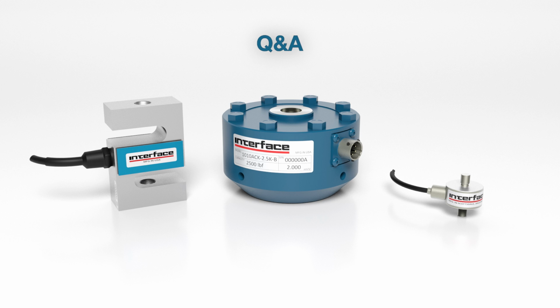Does the 150% apply to all models of load cells? This is going to be a model-specific question. It's going to be referenced on the data sheet for each specific load cell. Again, the recommendation is to size the load cell so the application doesn't require exceeding the actual rated capacity of the cell. I do want to say that a lot of our lower capacity minis, which wouldn't be the low profiles, do have higher overload. We are aware that as capacities go down, it's often easy to damage a sensor just installing it. So our SMTs, SMLs, a lot of those have 10 times safe overload. So not just 150%, but 1,000% safe. Best place to verify that, again, is on the data sheet.